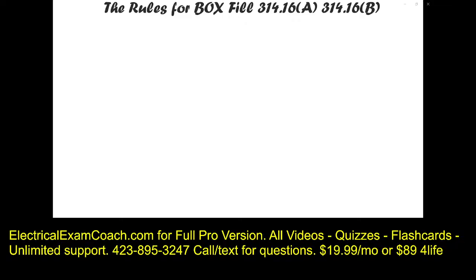We're going to learn how to count conductors now for our box fill calculations. We have to accommodate for each wire and then also for the different devices and fittings that we use out in the field. We're not going to be dealing with equipment grounding conductors at first. We're going to calculate those separately at the end of this slide. So now we're dealing with only neutrals and hots.